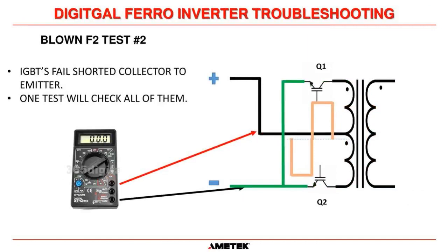So it's even easier with the digital ferroresonant type system, which we have here. This is what we call our SE system, SE and SV type UPSs. They use the transistors. And again, the primary of the transformer, when this thing is shut down, looks like 0 ohms. So the collectors of the two transistors, that's the right side of the transistor, all appear to be in parallel.